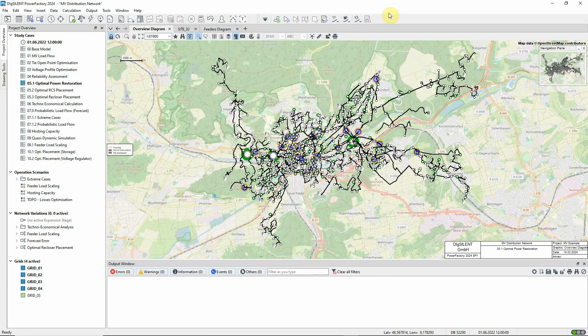In this video we'll look at optimal power restoration, which is part of the reliability analysis module. Optimal power restoration can be used to determine the best sequence of switch events to restore customer supply as efficiently as possible following fault clearing and faulted equipment isolation.